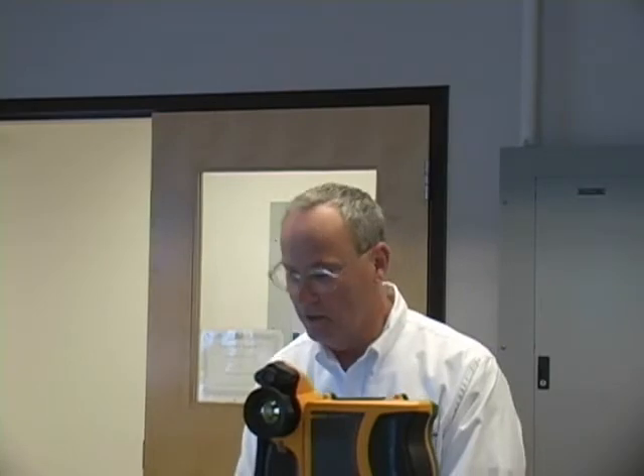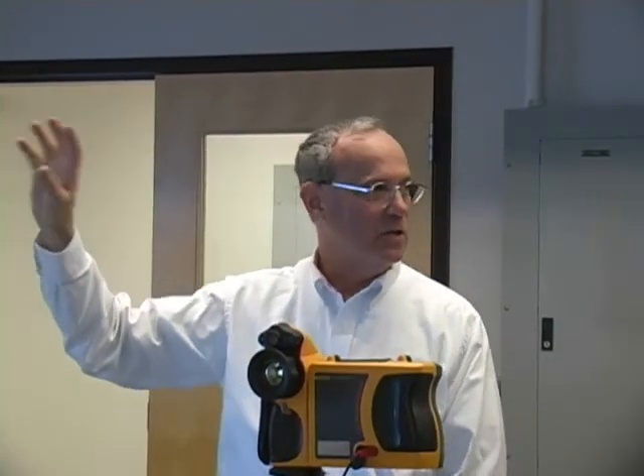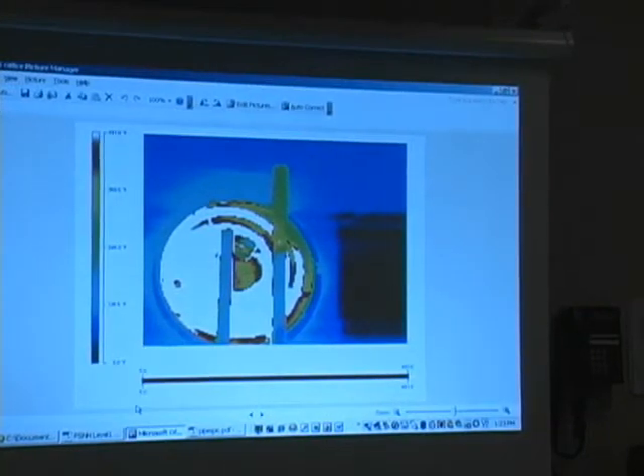And it's telling me it's not that hot. I wouldn't touch it. So here's a case that demonstrates very well. The top part of the pipe is black. It's giving almost perfect emissivity. There are no other components to that. That's pretty close to the temperature. The shiny part, anybody's guess.